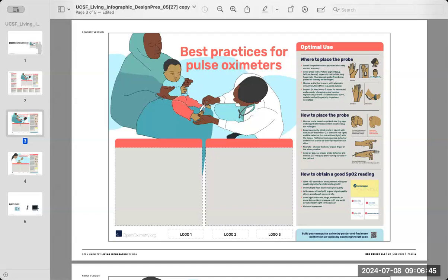My hand is lowered. Mike, my concern on what you're now projecting, which is number 3, but it may also exist on number 2, is that manufacturers, to my knowledge, have not considered the Great Toe to be a good site, and we don't have anything reflecting that on the right-hand side. But there are multiple other sites on the foot. So maybe have the graphic artist on number 3 fix that. It also exists on number 2, and I don't know what number 4 looks like, but just make sure that the probe placement matches the routine use.